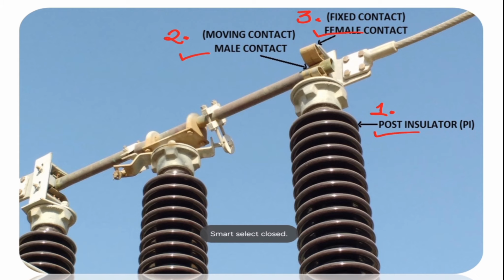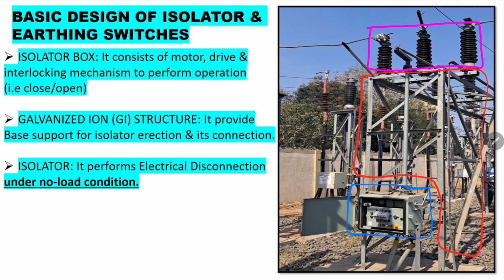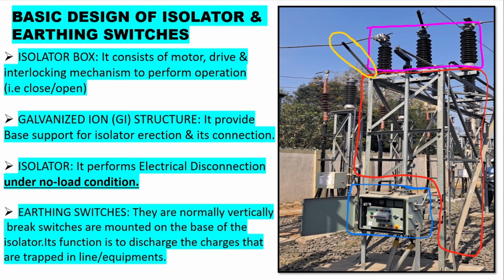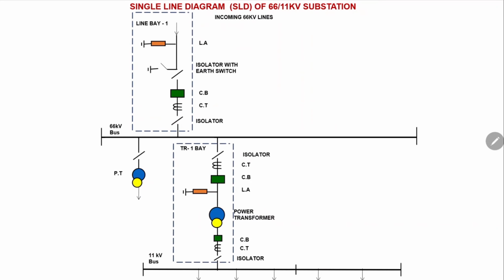Now let us get back to our basic design, and next are the earthing switches. Earthing switches, as shown here, are mounted on the base of the isolator and their function is to discharge the trapped charges. Depending upon the voltage class, the isolator design or dimensions can be different, but the basic structure, the basic parts and the basic logic will always remain the same.